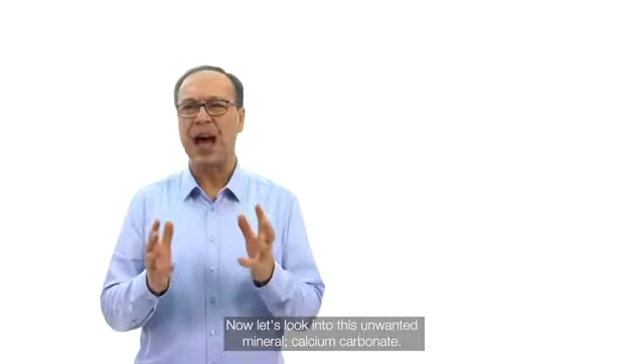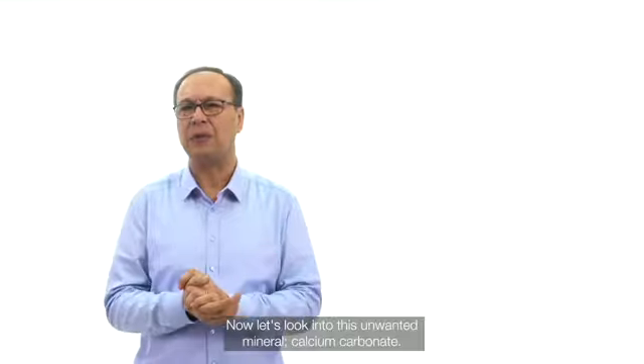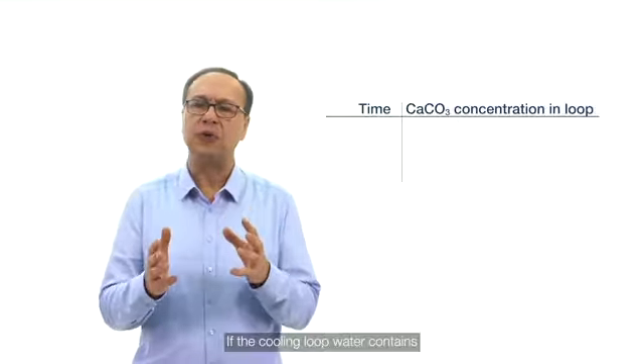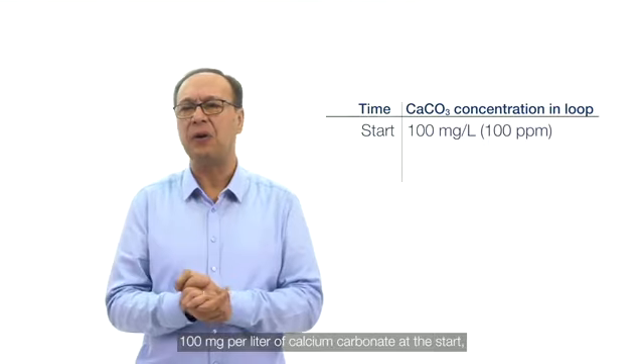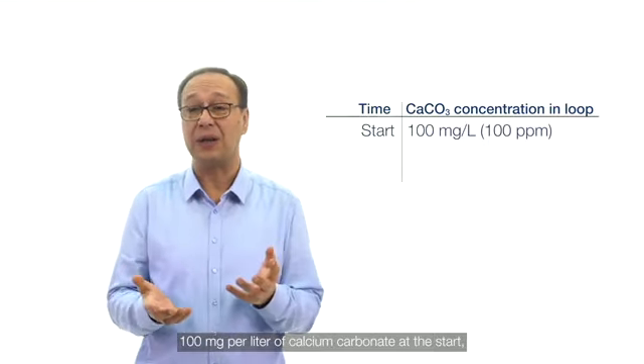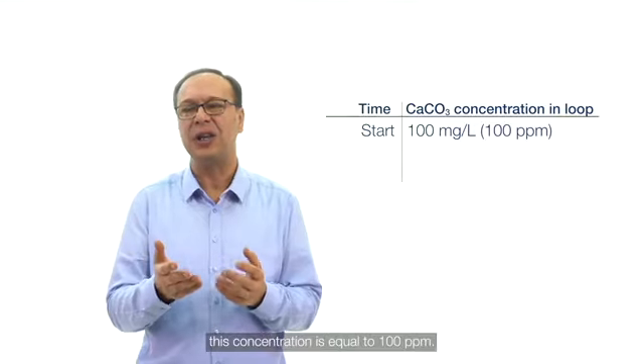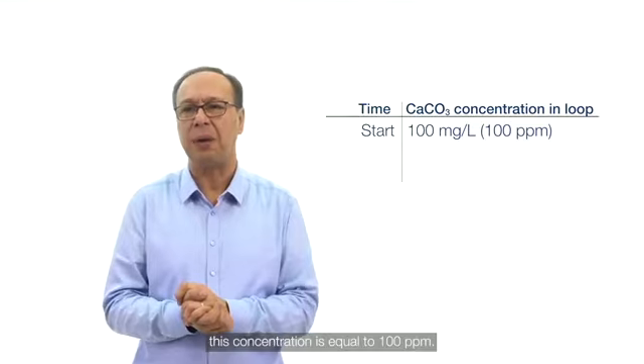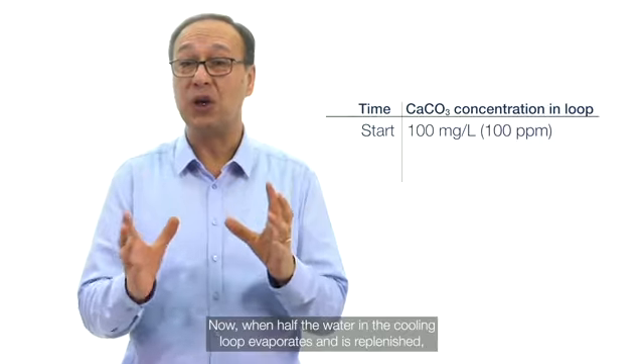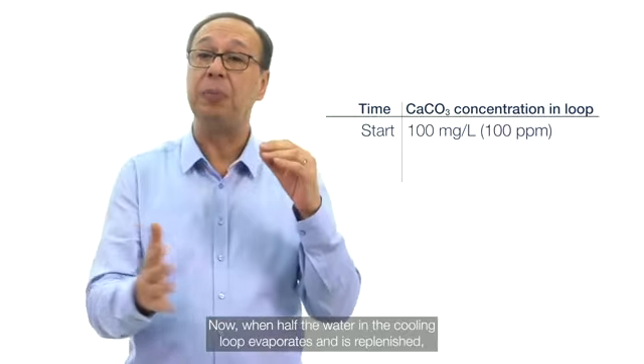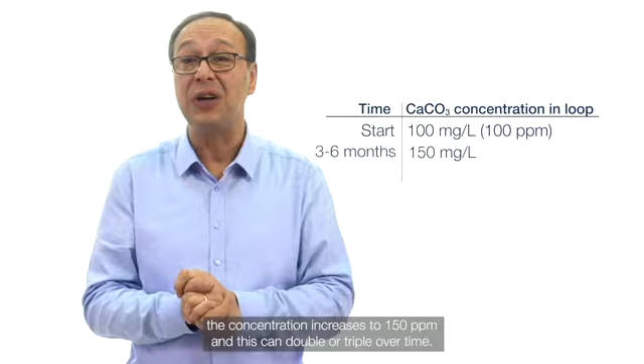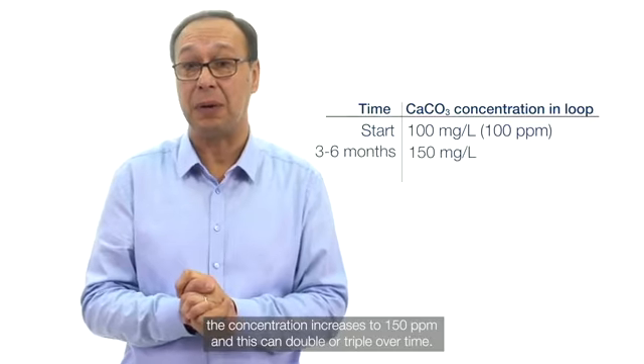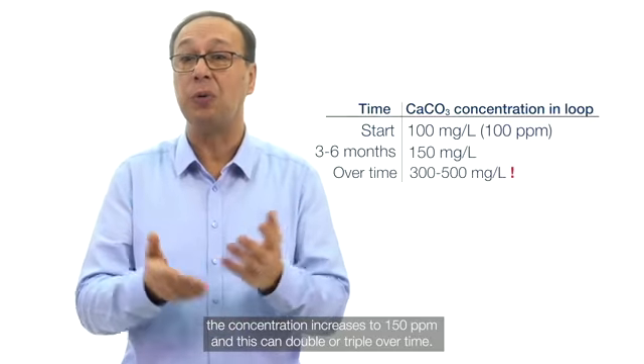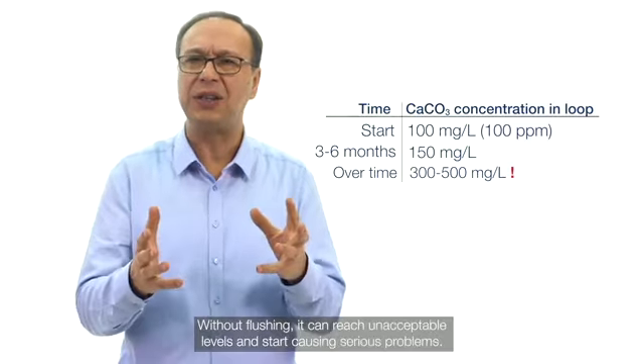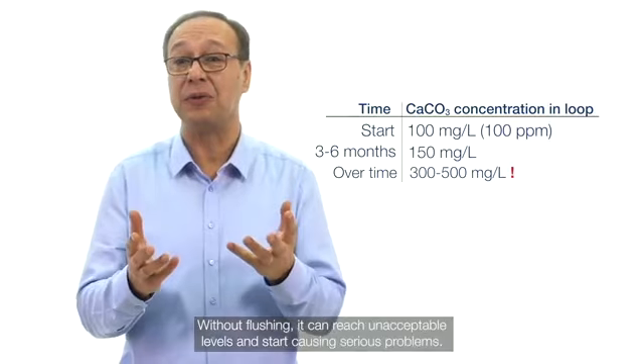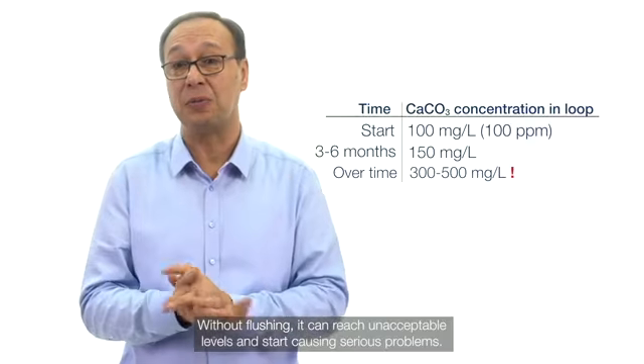Now let's look into this unwanted mineral, calcium carbonate. If the cooling loop water contains 100 milligrams per liter of calcium carbonate at the start, this concentration is equal to 100 ppm. Now, when half the water in the cooling loop evaporates and is replenished, the concentration increases to 150 ppm, and this can double or triple over time. And without flushing, it can reach unacceptable levels and start causing serious problems.